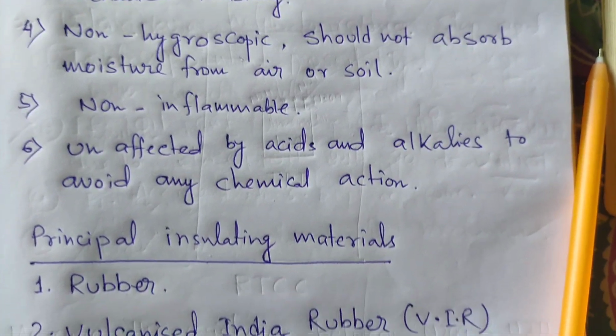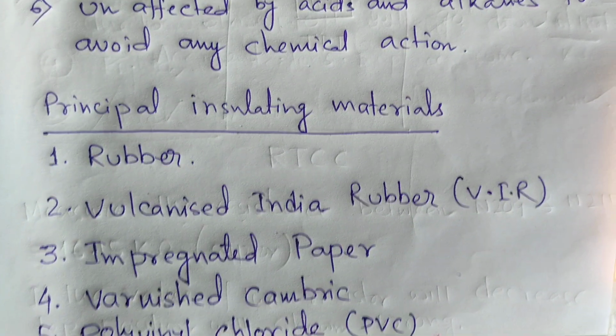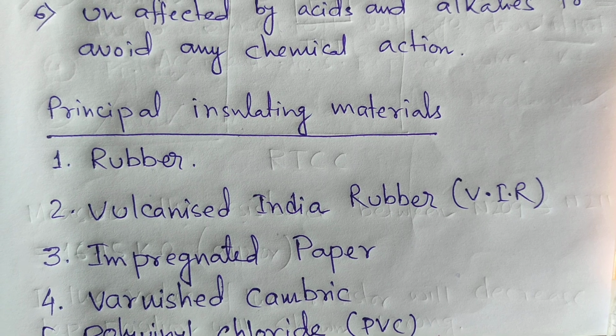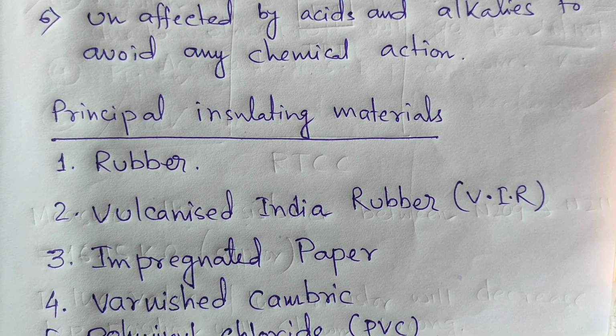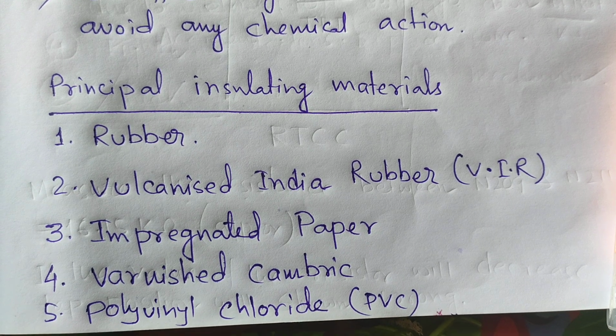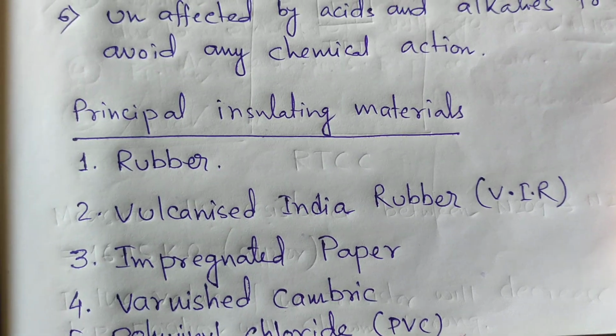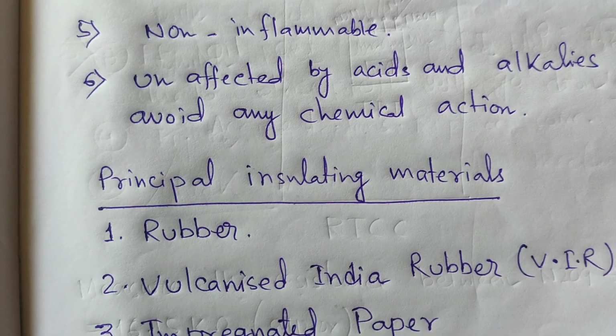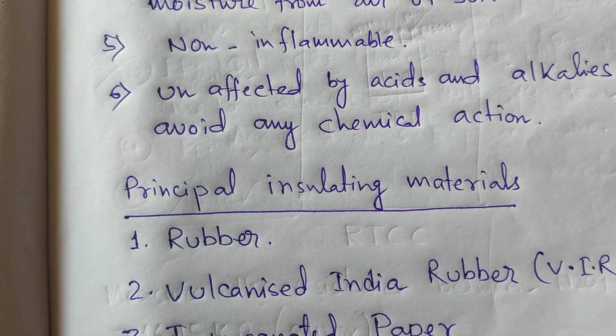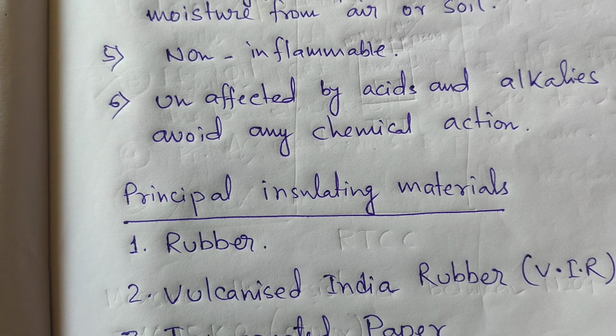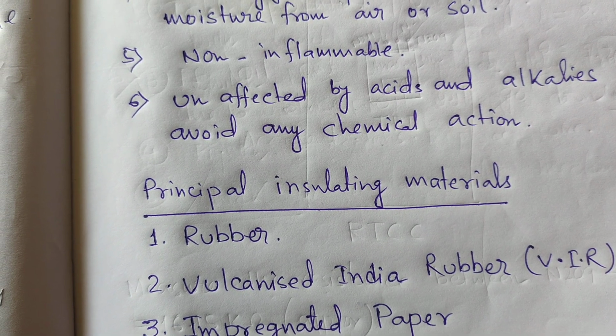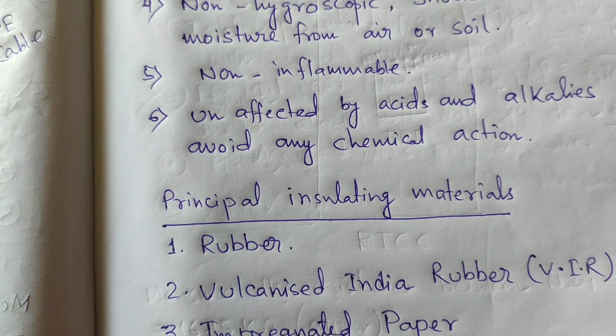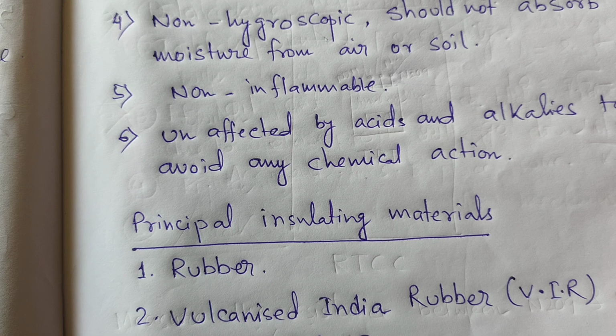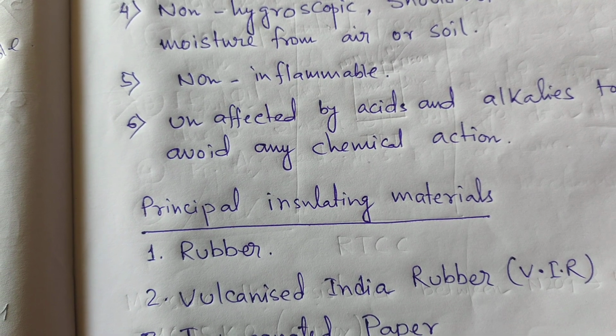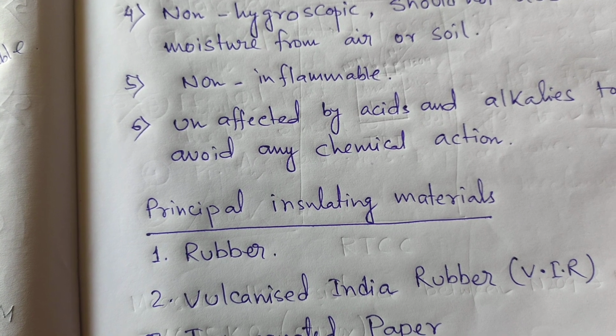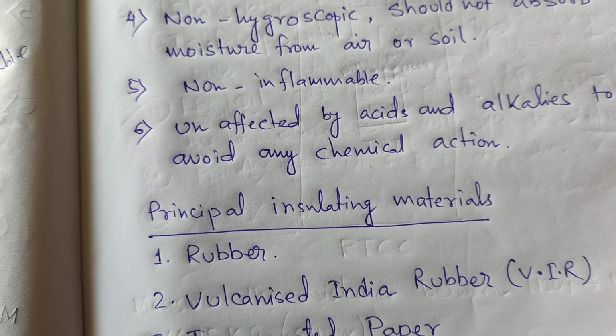Also, the principal insulating materials. The principal insulating materials are rubber, vulcanized India rubber, impregnated paper, varnished cambric and polyvinyl chloride. Rubber may be obtained from the milky sap of tropical trees, and it may also be produced from oil products. It has a relative permittivity varying between 2 and 3, the dielectric strength is about 30 kV per mm, and the resistivity of the insulation is 10 to the power 17 ohm centimeter.